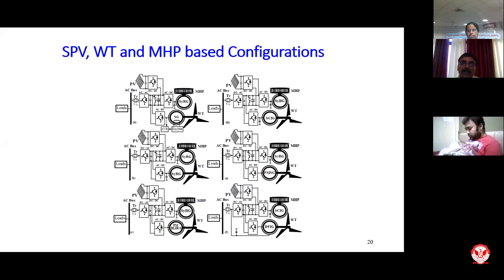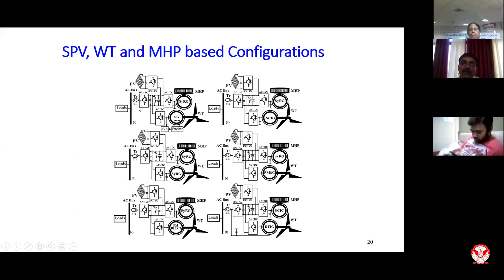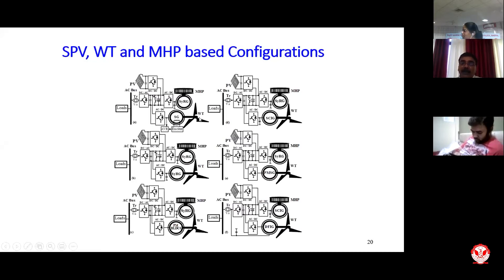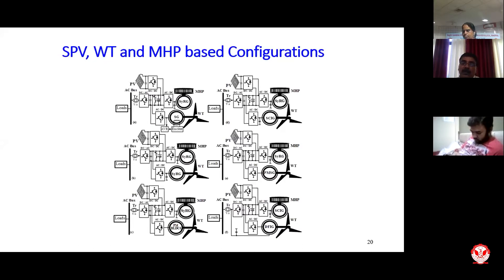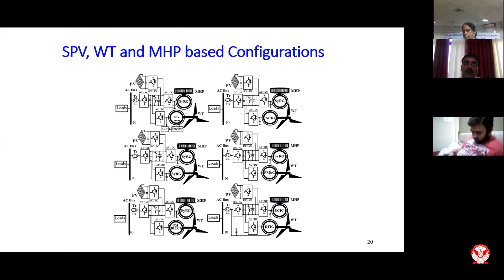A similar combination can be used for three sources: wind, water, and solar. Most connection points are on the DC side to avoid synchronization issues. These three sources can have priority management — in daytime, photovoltaic should be operated at most; when wind is available, wind should be operated; when neither wind nor solar is available, micro-hydro should be operated. A small reservoir can store water so that when both wind and solar are unavailable, micro-hydro meets the load — a kind of generation-side management.